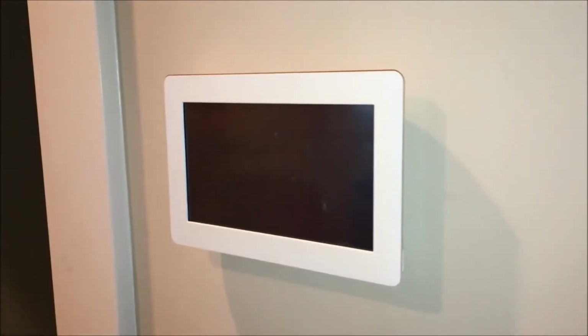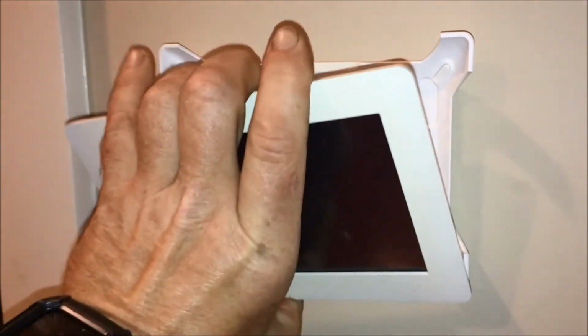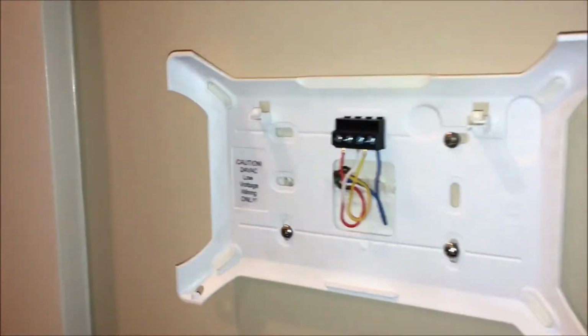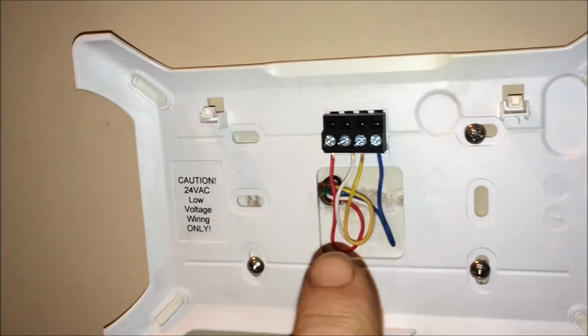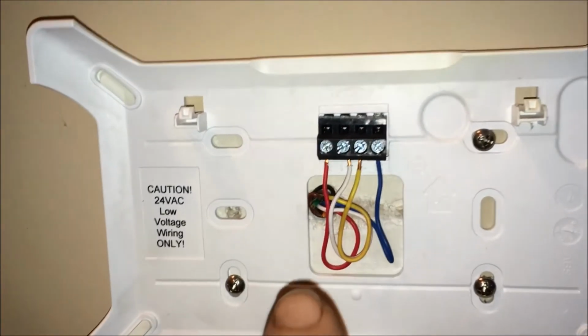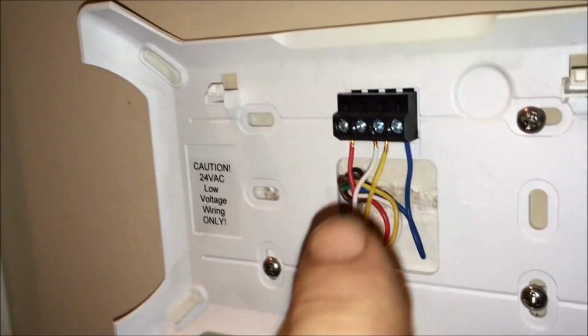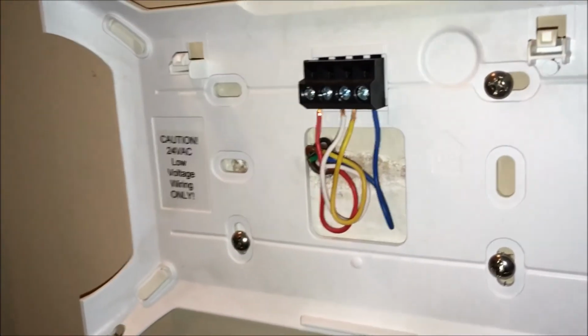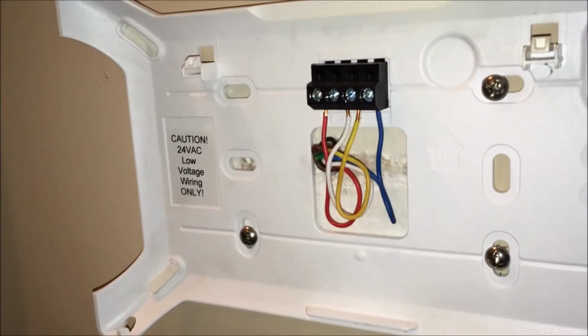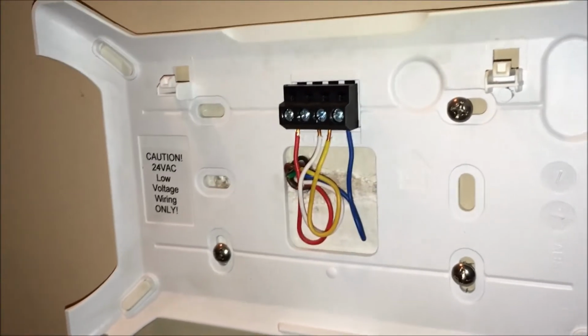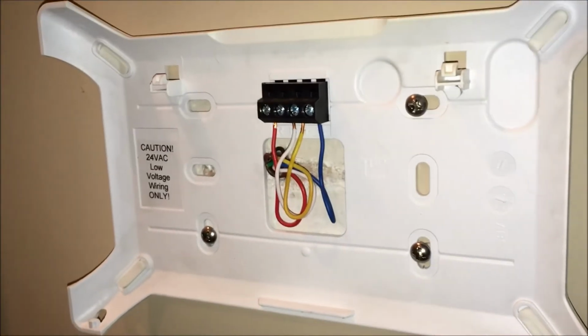Next thing I learned that I needed to check was to make sure that I was getting power to this panel. So you just pull this off, and you check voltage on these leads, and there's a description in the testing procedure online that you can find. What I found was that I had no voltage going to this control panel, the thermostat. So that told me something's going on up at the air handler unit in the attic.